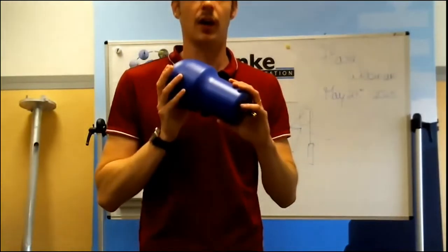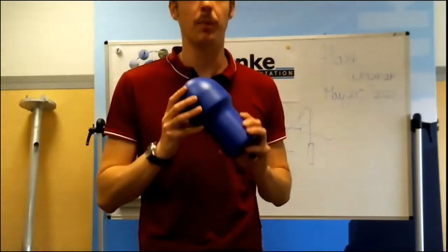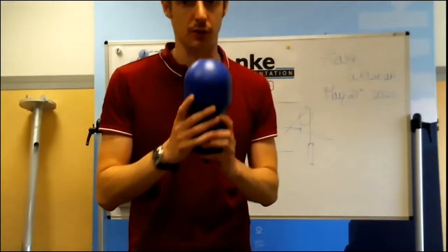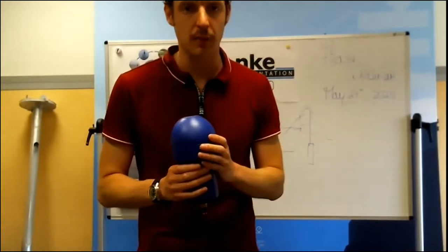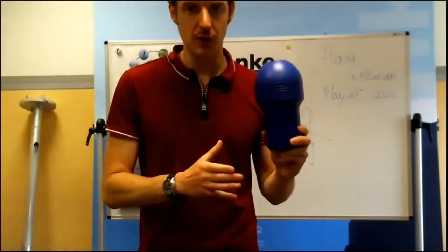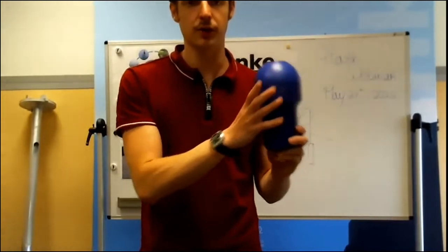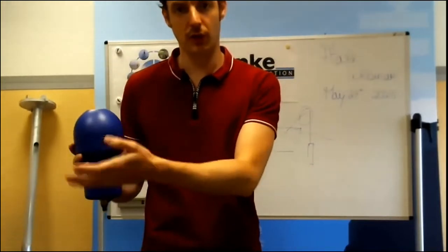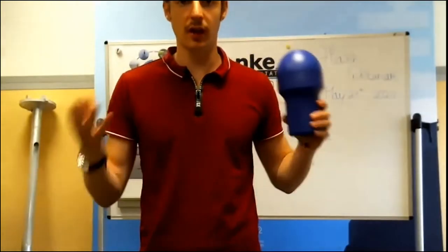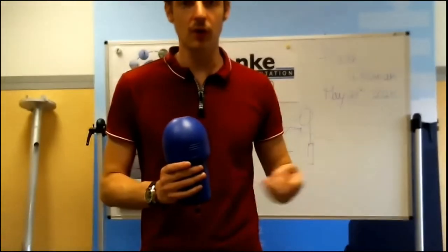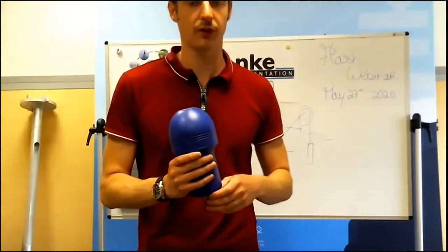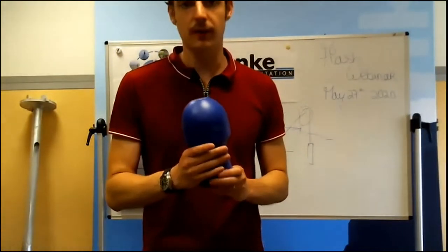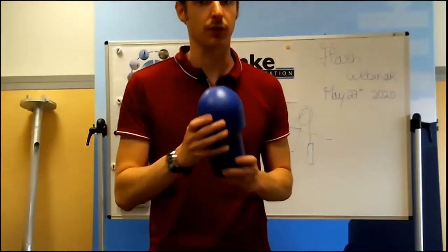And what is very interesting is that both the WiMo and the transmission module are only powered on their own alkaline batteries. So the transmission module will use its own alkaline batteries, and the WiMo will use its own alkaline batteries. And you can have month-long or year-long monitoring stations, depending on the fouling, of course, based only on alkaline batteries on these two modules.